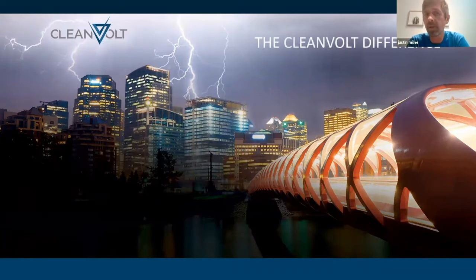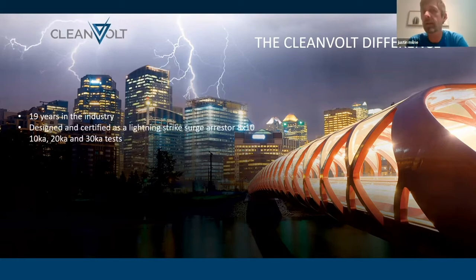So the CleanVolt difference: we've now been in the market since 1998, so we're in our 22nd year. When we were originally designed and certified, we did so as a lightning arrestor. The reason this is important to keep in mind is because it shows that CleanVolt has the ability to handle large catastrophic events, and as long as we don't expire our kA rating within a very short period of time, less than a second, we survive to protect in the exact same manner on the next event.